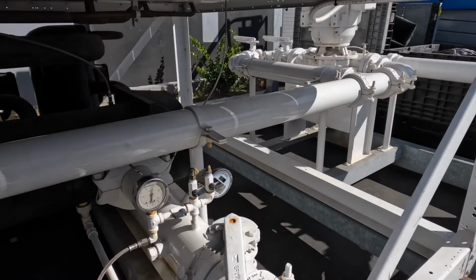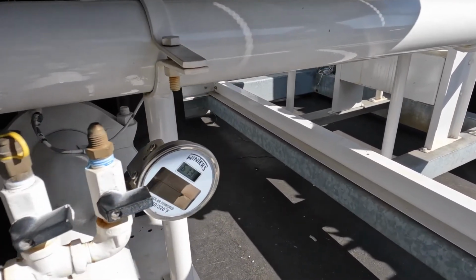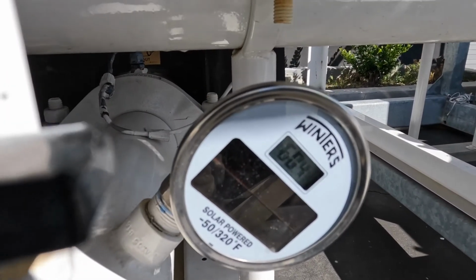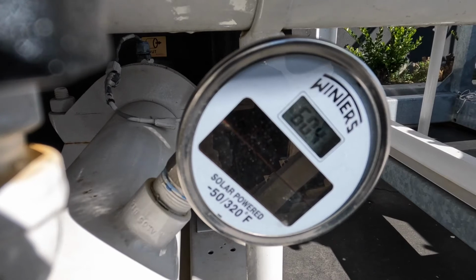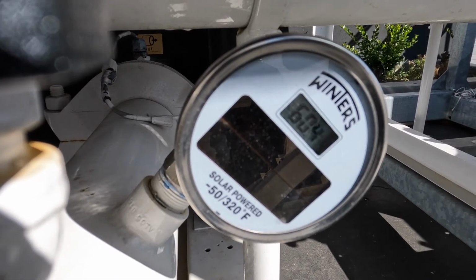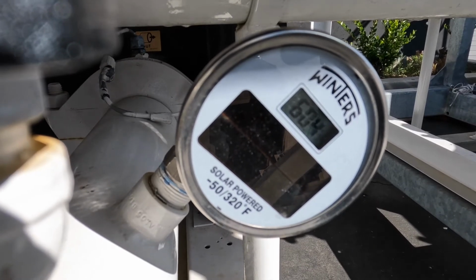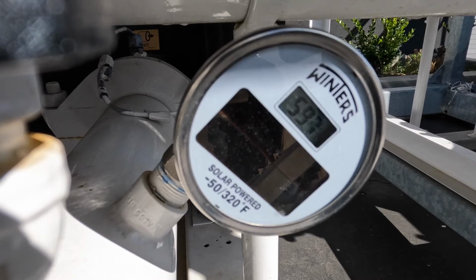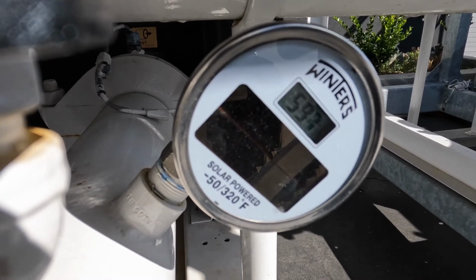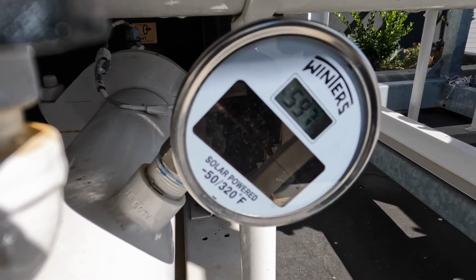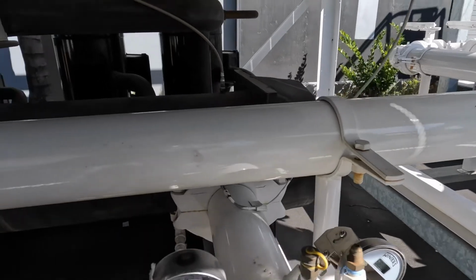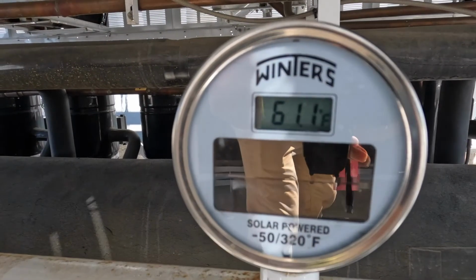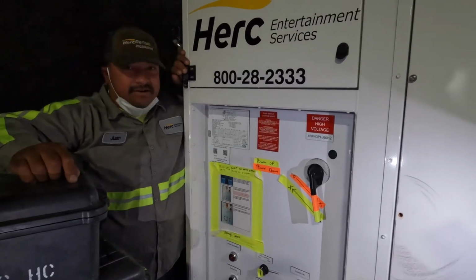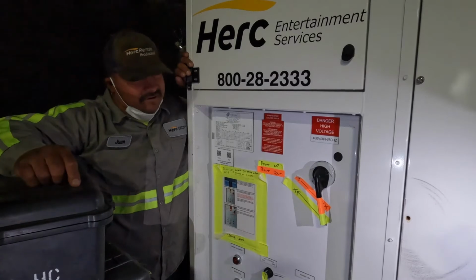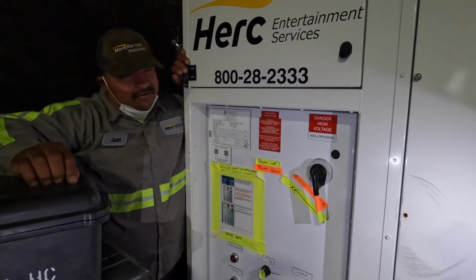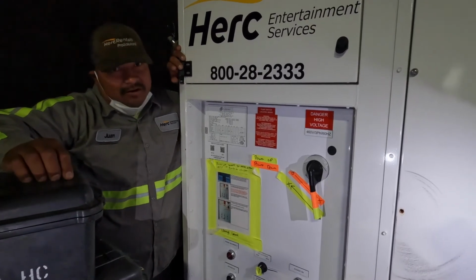So now that we're starting the chiller up, what you're looking at is the water temperature leaving the chiller, going to the air handler inside the stage. Give it about 20-25 minutes for the chiller to lower the temperature of the water to below 60 degrees before you turn on the air handler. Now that our chiller is up and running, our water temperature is down below 60 degrees. The system has built enough pressure to operate.